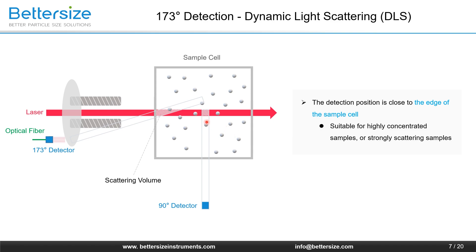When the detection position is close to the edge of the sample cell, the laser beam does not need to penetrate the sample, which can effectively minimize the multiple scattering effects of high concentration samples and ensure the accuracy and repeatability of the particle size results in the high concentration range. However, due to its optical design, the scattering volume is so small that it impairs the sensitivity of the instrument, and therefore the instrument is not competent to measure small particles, weakly scattering samples, or very diluted samples under this condition.